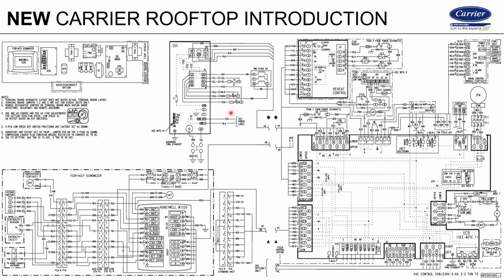So the unit's out there running, and for whatever reason, a dirty filter, and I'll talk some more about some of the reasons, whatever it is that caused that limit to trip, now it resets the IGC board. Now you as a service tech go out to the site, you open up the panel, you say, hey, my IGC board's got a solid red light, must be no fault codes, what's going on? And all of a sudden the unit starts up and runs. There's no history and there's no indication that it tripped on limit. So it wasn't the best plan out of the box the way they designed that. So that has since been corrected.